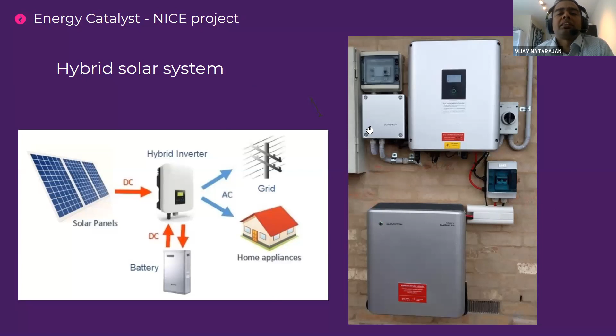Now, as I mentioned, there are three different scenarios in which we will operate this system. One is when the grid is down and the diesel generator is not generating, then we are mainly running from the solar and battery available in the community and the school. But when the grid is down and there is not enough energy, we will then use the diesel generator. When the grid is powered and the diesel generator is not generating, we will just run with our system independently, without the diesel generator.